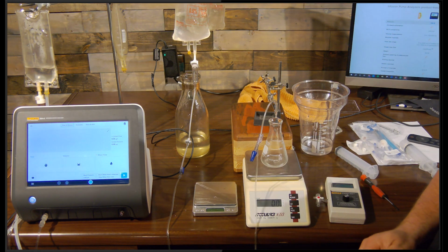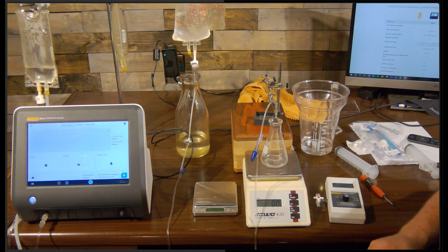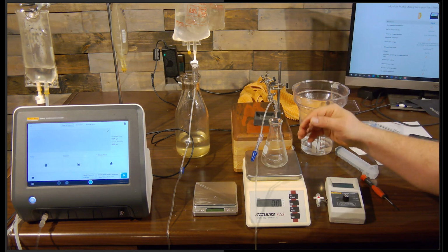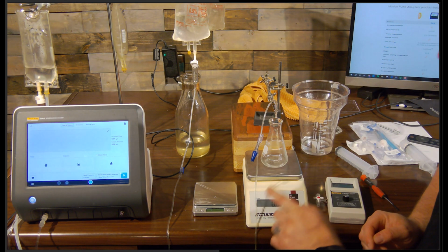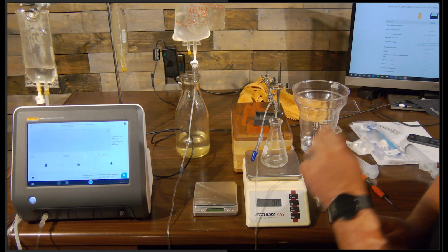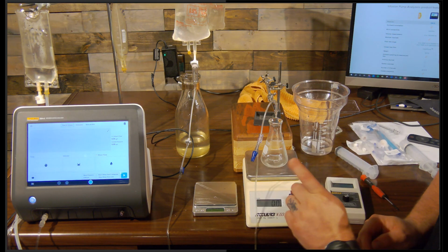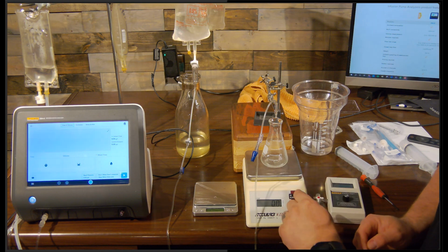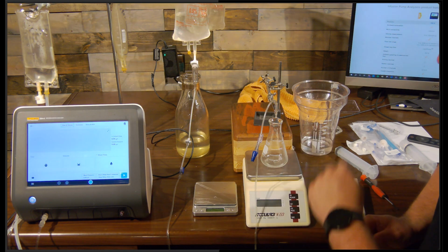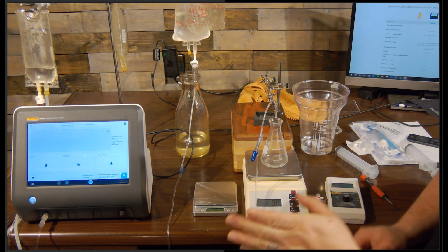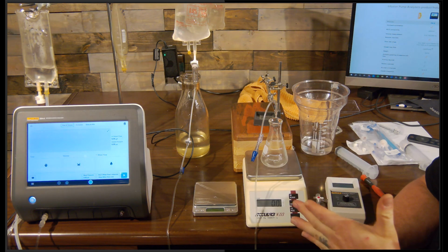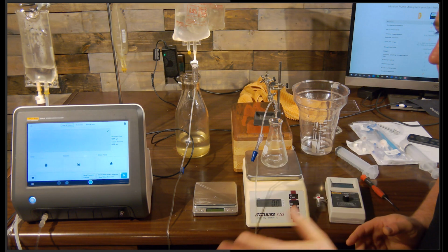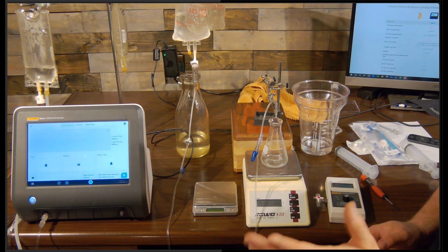And then before you start your next test, you have to remember to do the priming sequence if your infusion pump calls for it. Once the priming sequence is done, hit tare again to zero it out, do the test, but you have to be here while it's running. When that infusion pump completes, it's going to beep at you, and you need to be here because flow is a volume over time. So if your infusion pump stops exactly at the end of that test, you might be okay, but most infusion pumps have a KVO, keep vein open.